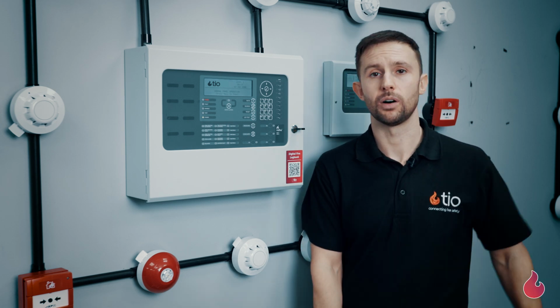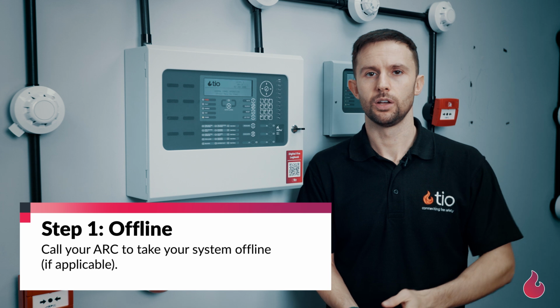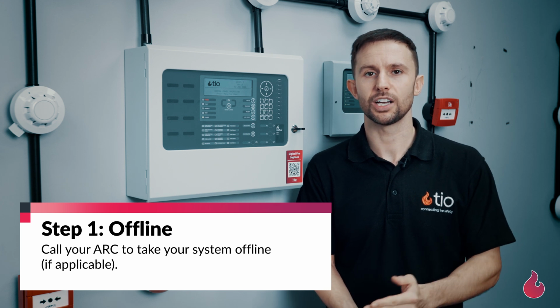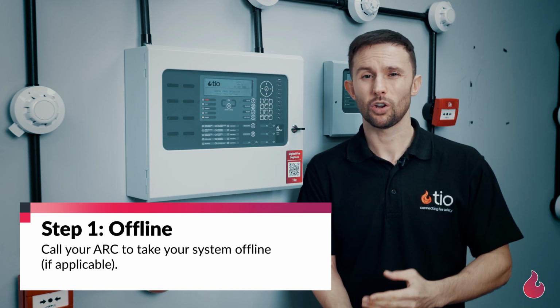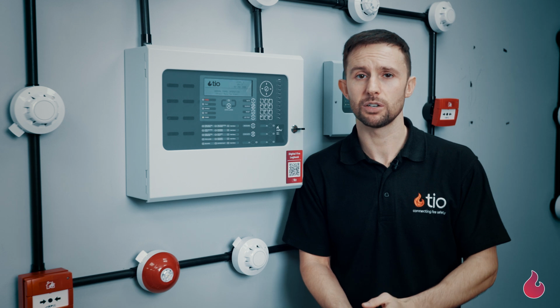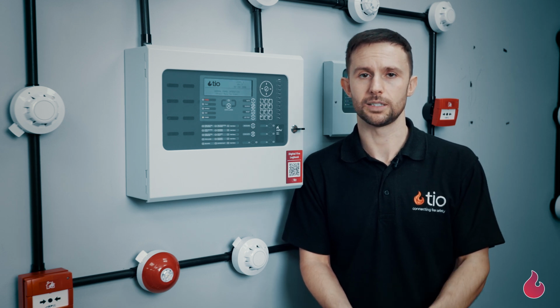Now that I've explained all the preparation phases, let's do a live weekly test on the fire alarm panel behind me. Step 1 is to call the ARC. So if you are connected, you would call them up. You'd often give them your postcode and a PIN number or password. You're going to ask the operator to temporarily take your system offline while you do a weekly test.